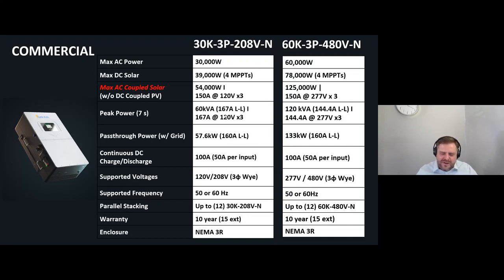When Sol-Ark first came to market, it was so much simpler than its predecessors that installers said, wow, this is the easiest to use inverter system ever. Now when you go with, say, an Enphase or a Tesla system, they may appear more easy or basic, but they don't allow as granular control as the Sol-Ark does. What was really nice with the Sol-Ark controller is when net metering 3.0 came out, we didn't have to change anything about our software or control scheme. You just pull up the time of use settings, tell it to sell back to the grid between 6 and 8 p.m., and you're good to go. Very simple, but very powerful.